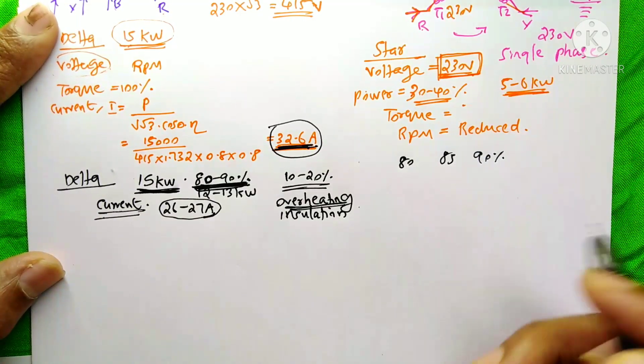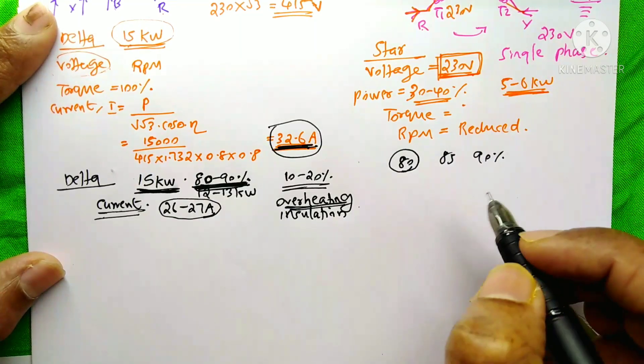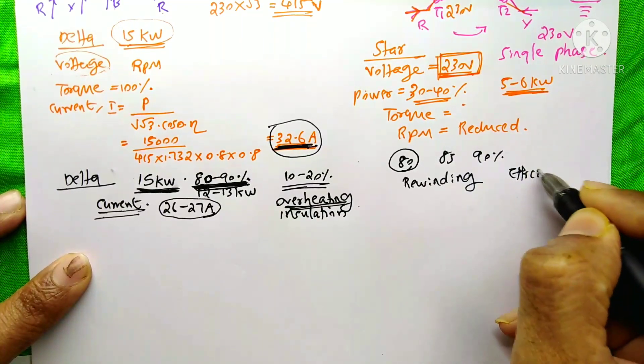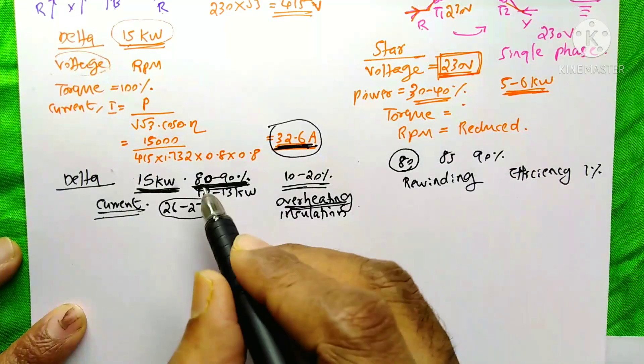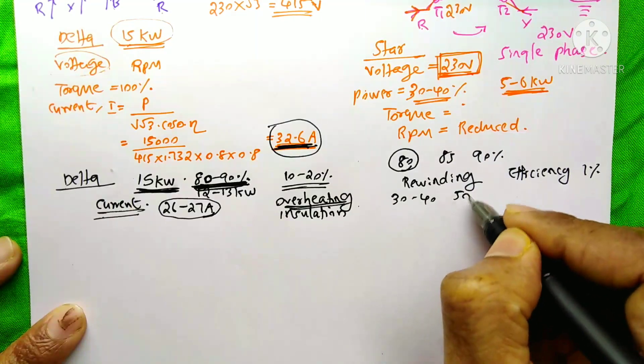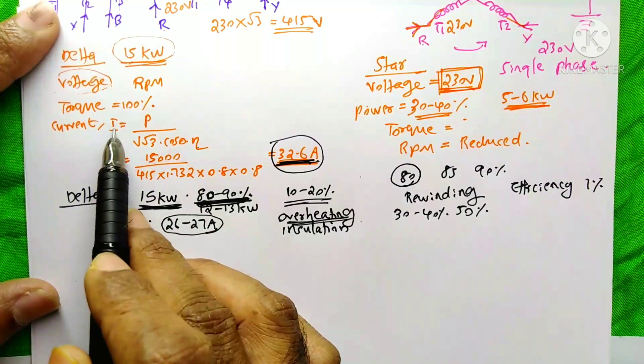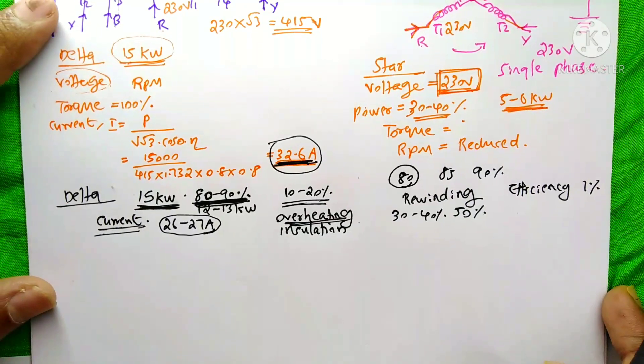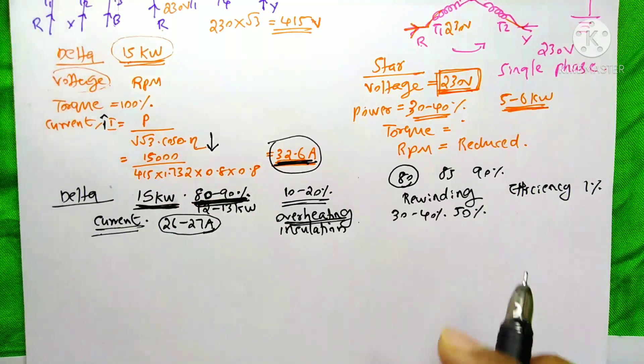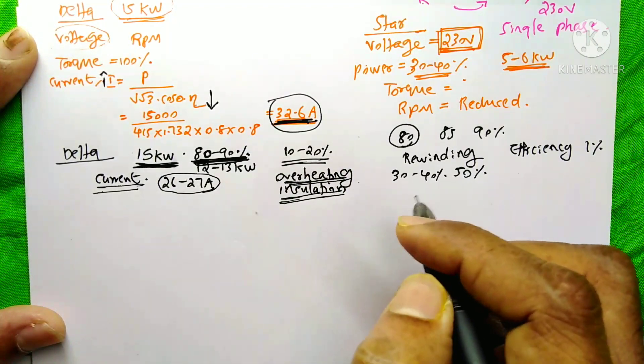The efficiency shown on the motor nameplate — 80%, 85%, 90% — is fixed and cannot be increased, but it can decrease for certain reasons. After each rewinding of the motor, efficiency reduces by 1%. Also, when the motor load drops to 30%, 40%, or 50%, efficiency decreases. From the current equation, efficiency and current are inversely proportional — whenever efficiency decreases, current increases — and whenever current increases, the motor overheats and insulation failure occurs.